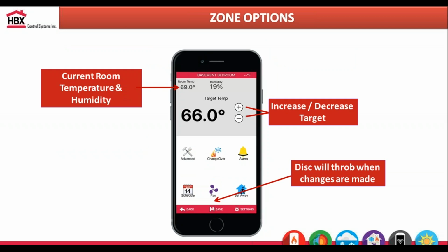For different zone options, you can simply increase or decrease the options. There's home and away modes. So if you're on vacation, or zones that you're typically not using through the day, you can put those into an away mode. So typically we'll go into a cooler mode, and then you'll just activate them when you are utilizing them. You do have the options to set alarms. So you can put a temperature trigger for below or above a certain temperature, and that will give you an option to get email notifications saying, hey, your domestic hot water tank just went below 100 degrees. You may want to check it out. So you do have that capability of getting alarm notifications.